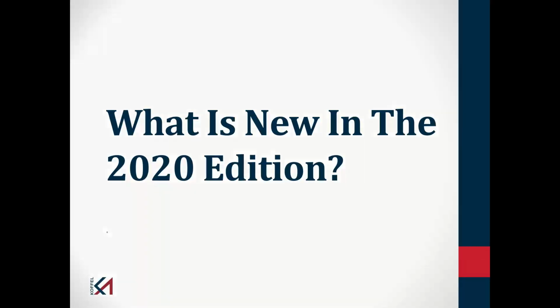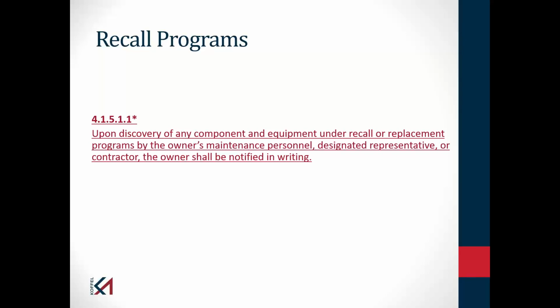or rack storage. With regard to NFPA 25, one of the things the committee has debated for several editions is what's the role of the inspection entity when it comes to recalled sprinklers. And we finally settled on some language that actually is in the owner's responsibility section in Chapter 4, but it does say if anybody discovers that there are sprinklers in a building that are subject to a recall or replacement program, the owner is to be notified in writing.